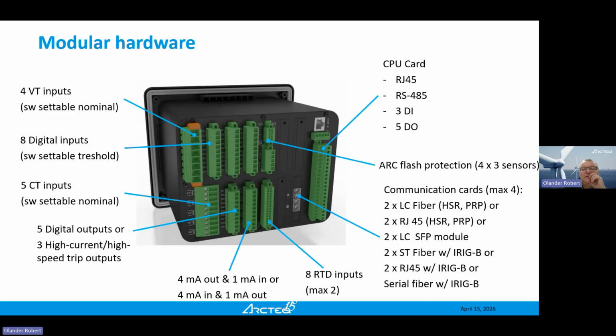We can take a look at them here. So then what you can add with hardware options is, of course, depending on the type, it will have either 5 current inputs, 5 CT inputs, and if you need also voltage, then it will have 4 voltage inputs. And of course, you can add CT inputs so that you have 10 if you want to do the differential protection and so on and so on.